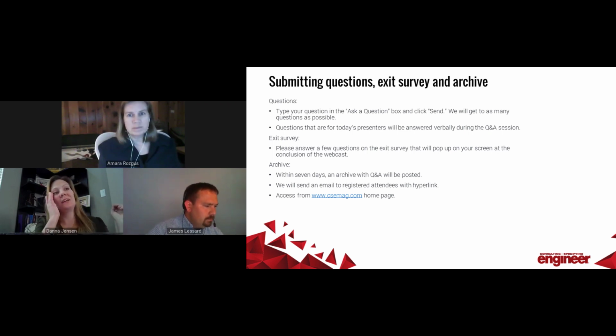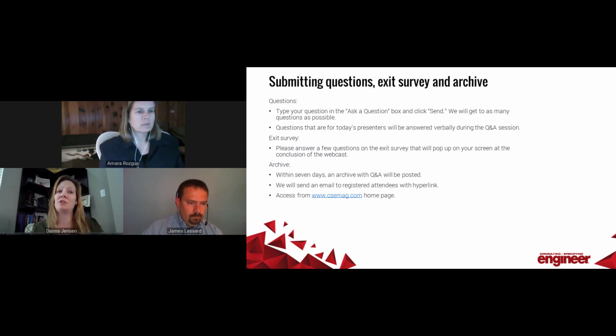Yeah, so great question. Like I mentioned, diesel fuel does have a shelf life. So when it's kept in a cool and dry location, such as a UL listed storage tank, it typically won't last longer than 12 months. It will deteriorate if stored longer than that. So yes, when you have those high capacity tank storage systems, when you're not using a lot of the fuel, you do need to clean the fuel. And a fuel polishing system is basically just a filtration system that separates out the water and removes any of the accumulated contaminants, sludge, even algae growth from the fuel. You can have on-site fuel polishing systems where they cycle as needed. But if you don't have a permanent solution in place, there are maintenance providers that will come in and pump out and filter out that fuel for you. It's just really important that the operators of these facilities do understand that, because if you have bad fuel, then your engines aren't going to operate when you really, really need them. So yes, fuel polishing systems, highly recommended.